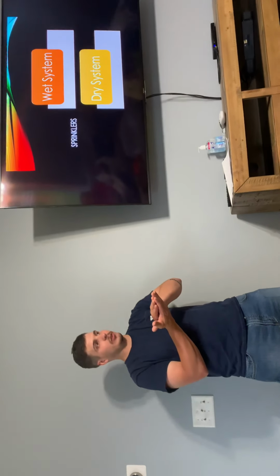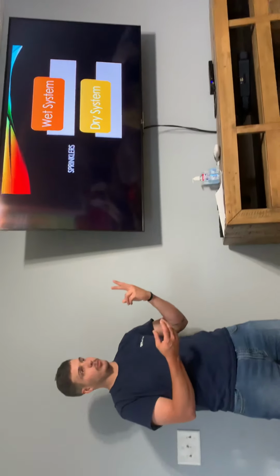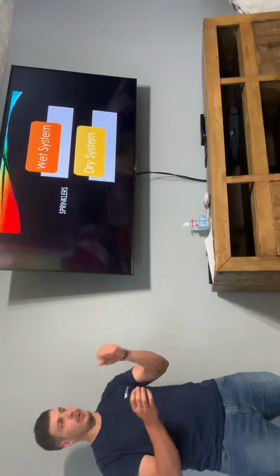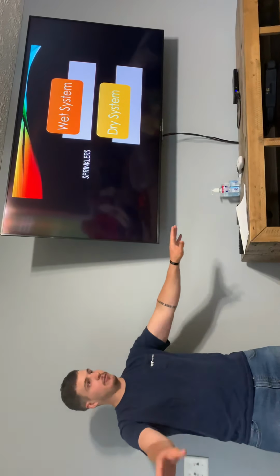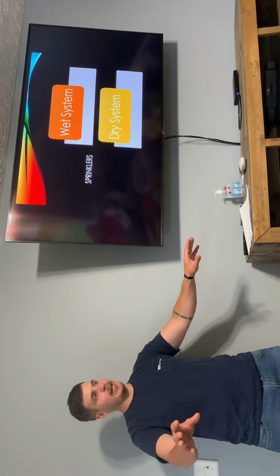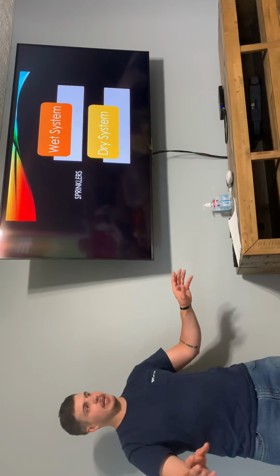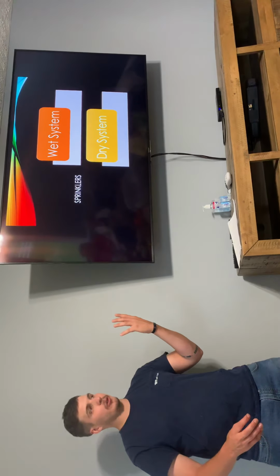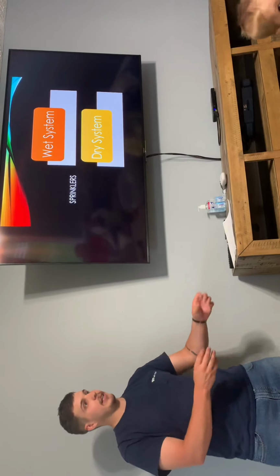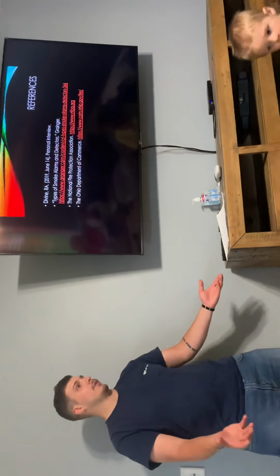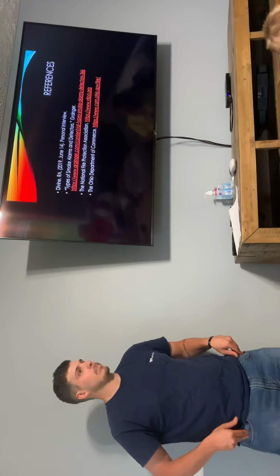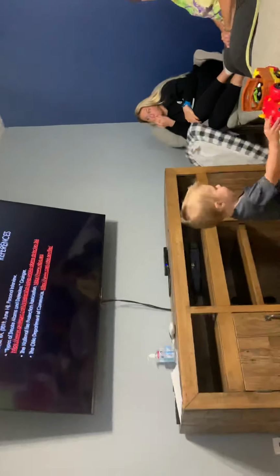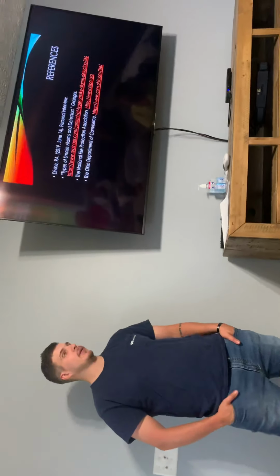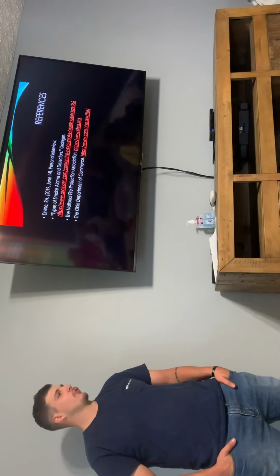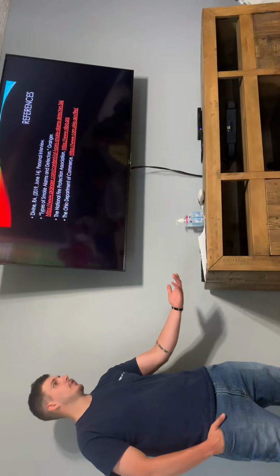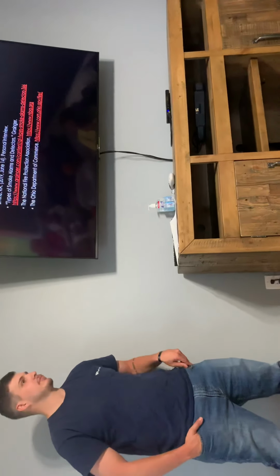Now when the alarm goes off, 2 alarms energize the panel, and the panel takes away the air and floods the pipes. When it floods the pipe, the only thing left to happen is the fire to melt the sprinkler head wherever it is in the building, and then that will help stop the fire, if not stop it. So the dry system doesn't consist of chemicals? No. That is a whole different ballgame. That's more special hazards, more for data centers or tech companies.